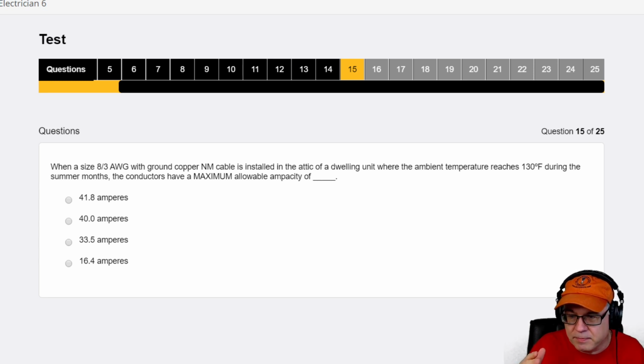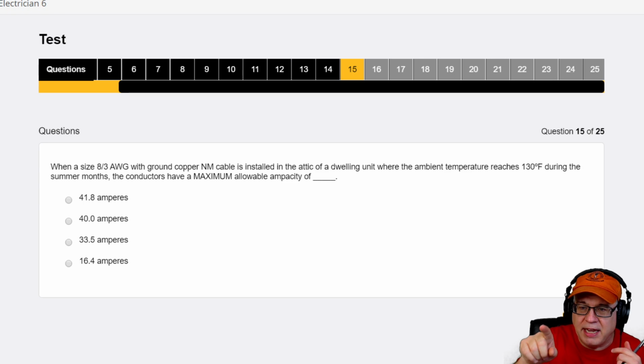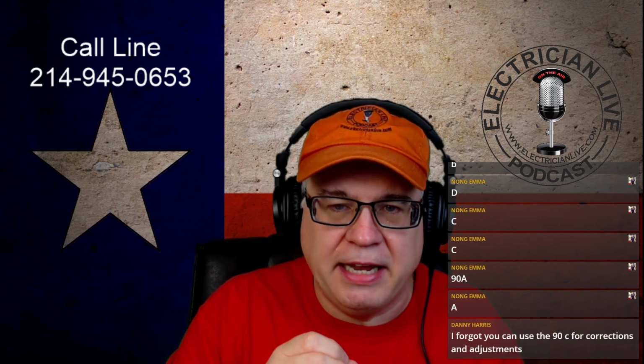All right. So you start from the 90, and when people ask me this, I guess this is special for all of you. This is important. When you're doing adjustments and corrections and you're using the 90 ampacity, all you're doing is an adjustment and correction to make sure that the conductor still has the acceptable ampacity under its terminal limitations after the conditions of use are applied. Okay? You with me? So in this case, let's say it was 55. Now I applied the condition of use, which was the ambient temperature. That dropped it to 41.8.